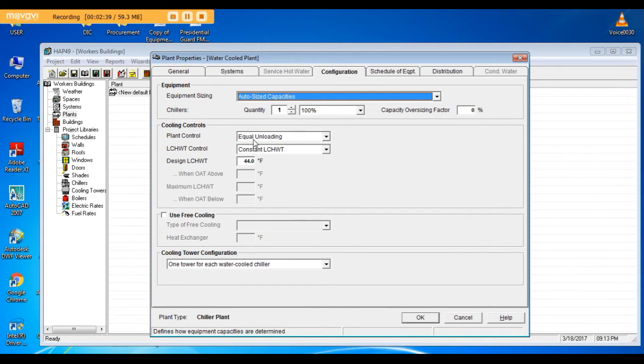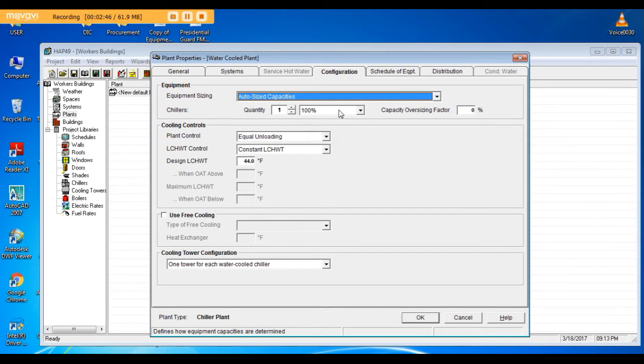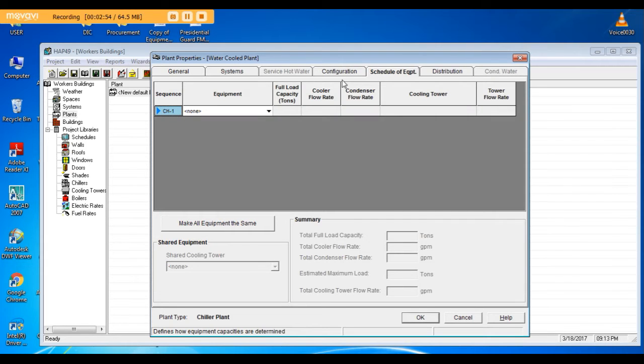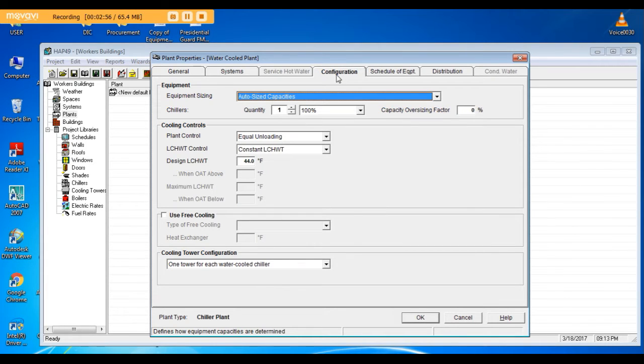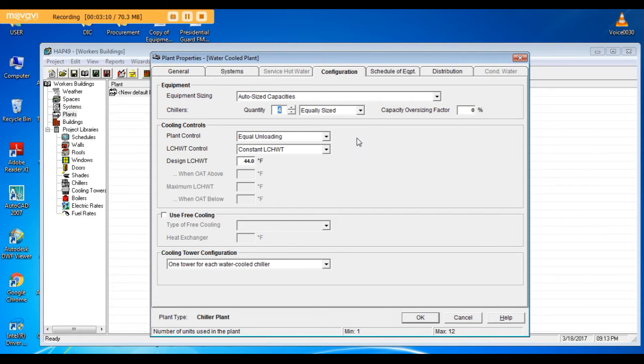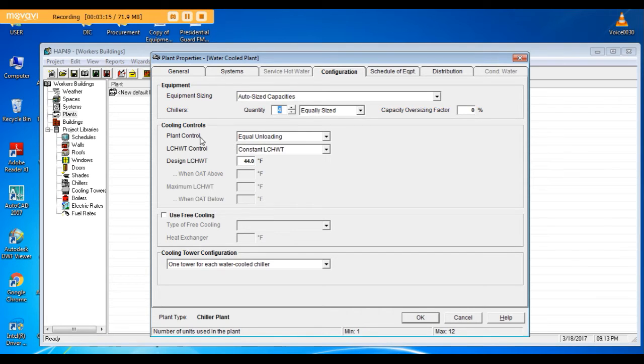After that, go to configuration. Equipment sizing I'll keep auto sized. The program will size the chillers. I'll put it four chillers. After the program sizes the chillers, you can redesign, increase or decrease the number. Now I will keep it four, equally sized plant control, equally unloading. I need all chillers to be equally unloaded.